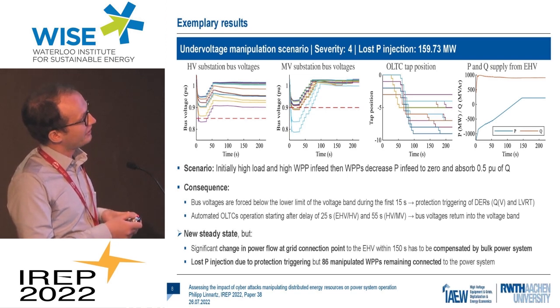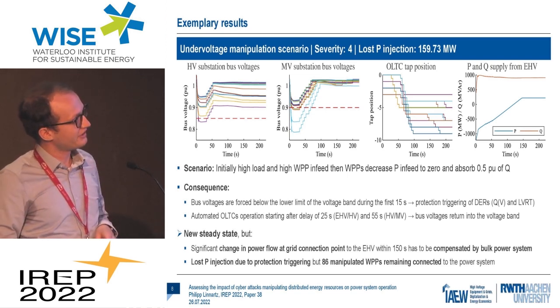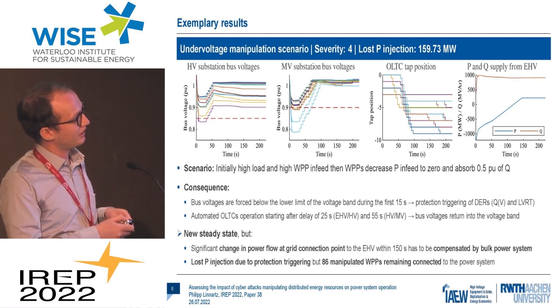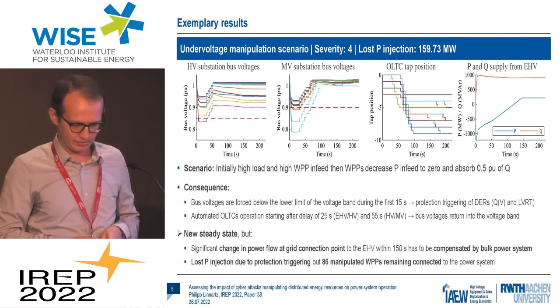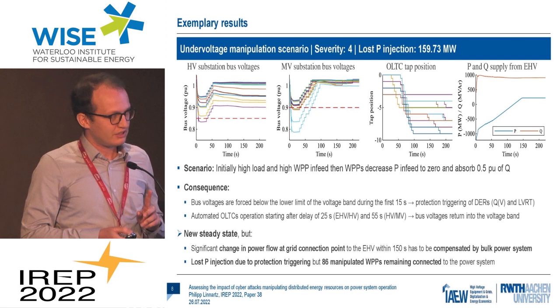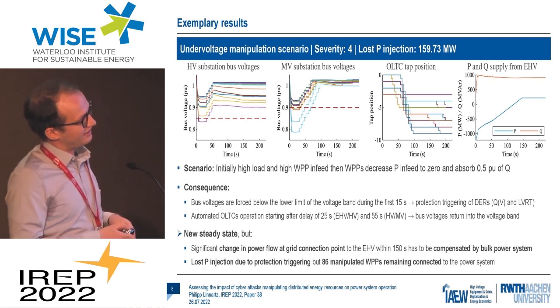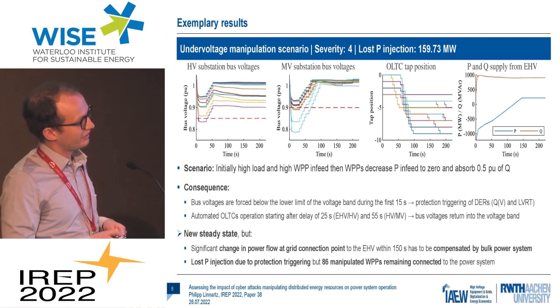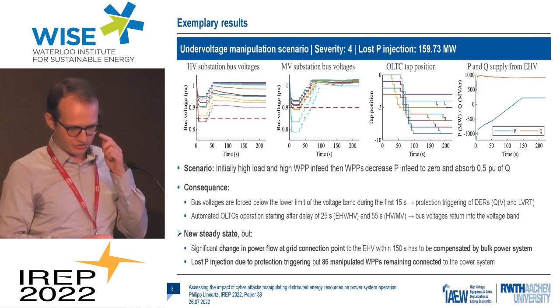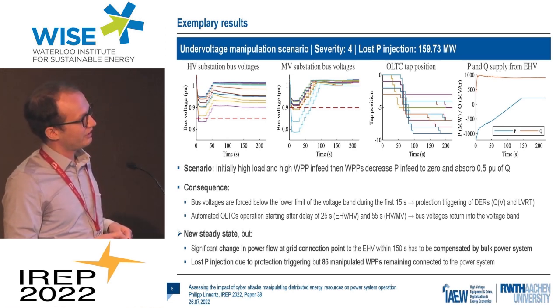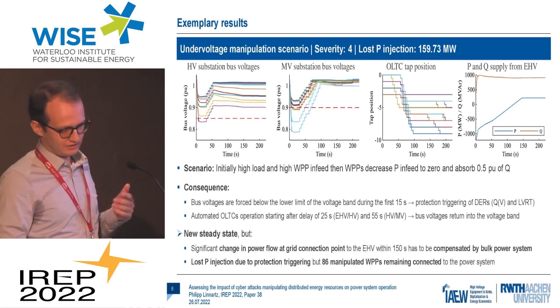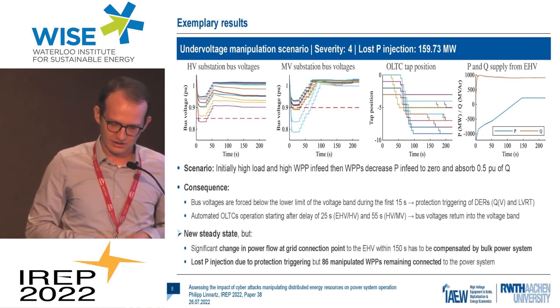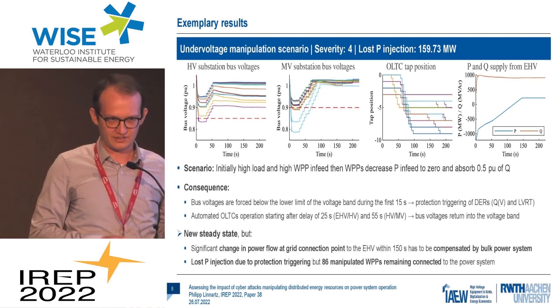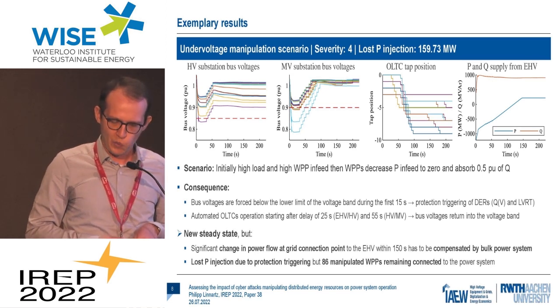What happens here is we assume automated OLTC operation, and they are actually able to bring back the bus voltages within the voltage band. However, this is a new steady state, and we have a significant change in the power flow at the grid connection point.